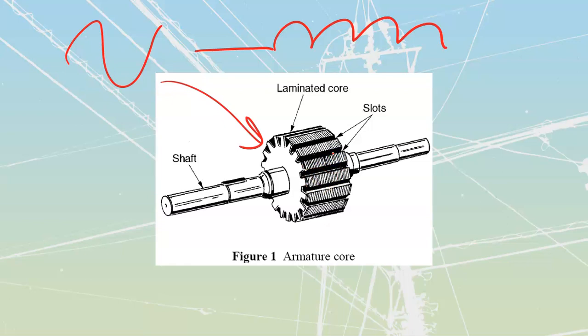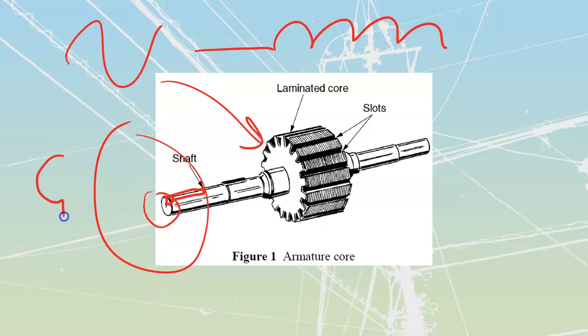We'll have a shaft that's usually steel — a harder material with lower eddy currents. We're not going to laminate it, but because it has much higher resistance, we drop the amount of eddy currents inside it. We place the thing on bearings and usually have what's referred to as keyways — little square sections milled into the shaft that allow us to couple and tie components onto it. We can slide a pulley over top, and the pulley itself has that same keyway inside it. We drive in what's called a key from the end, which prevents whatever's on the outside — the pulley — from rotating past the shaft.